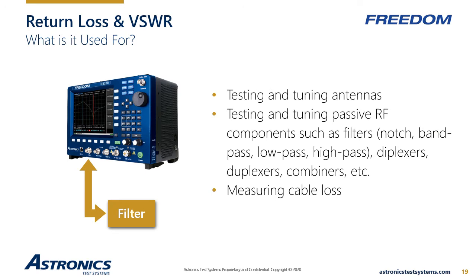The Freedom R8200 VNA's return loss and VSWR plots measure reflected signal levels over frequency. This type of measurement is the key to testing, aligning, and documenting antennas, RF filters, and cable loss. The Freedom R8200 return loss and VSWR plots must be set up to achieve a balance of accuracy and speed. Setup parameters and their impacts on accuracy and speed are discussed next.